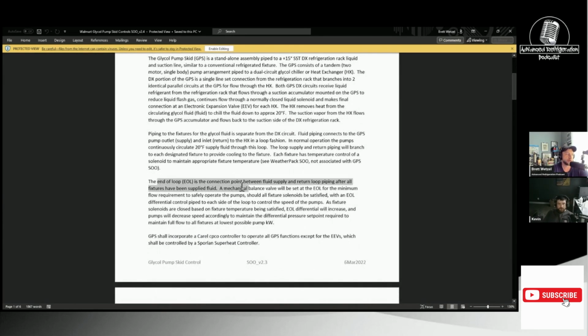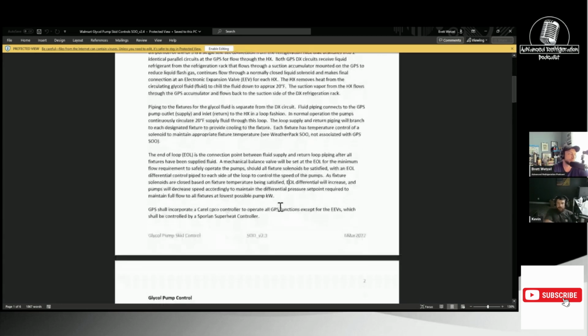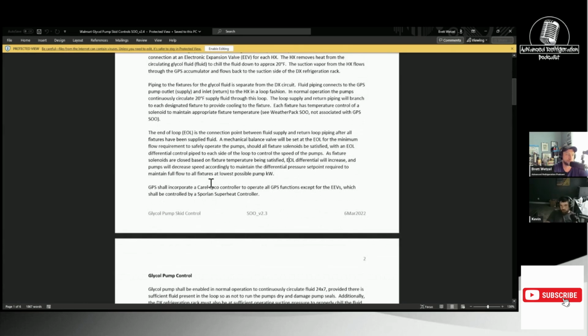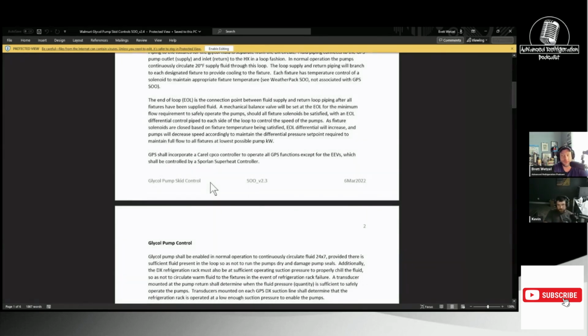So at the end of loop connection between the fluid return and supply, after all the fixtures have been supplied fluid, the mechanical balancing valve should be set. So you might have to just get in there and adjust that down, start closing it down to maintain flow. That would be my advice. It's like a quarter open right now. I think that seems too far. You think so? Yeah, because you don't even have all the cases hooked up yet. Yeah, I was questioning it.